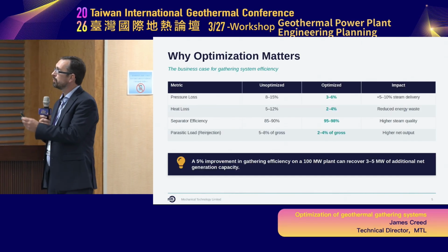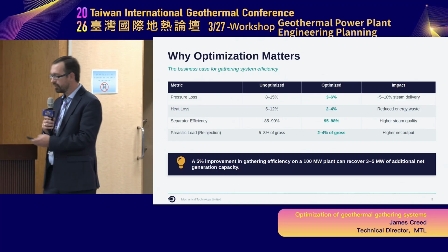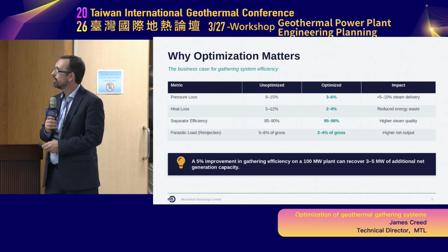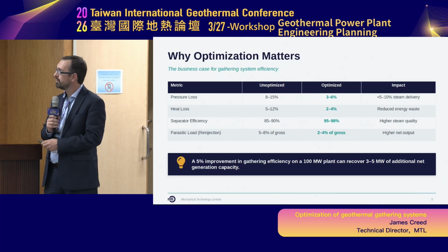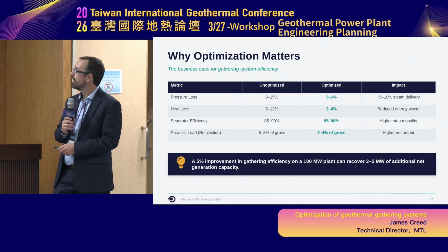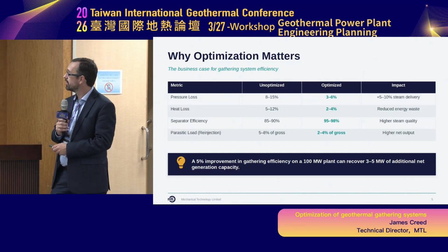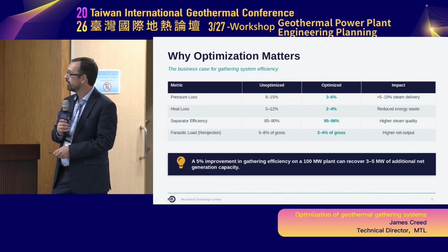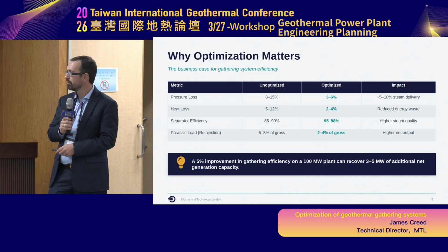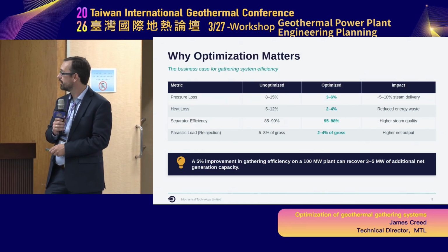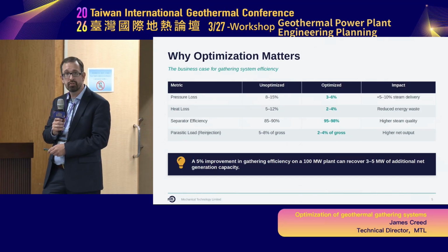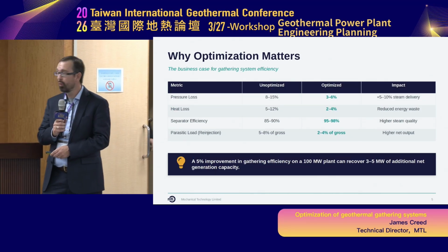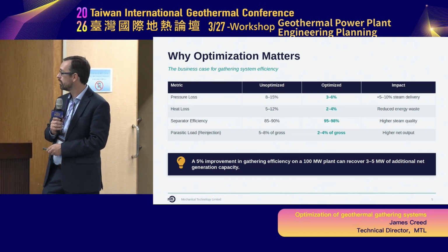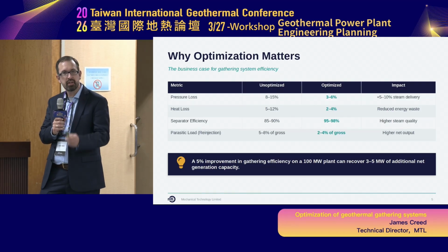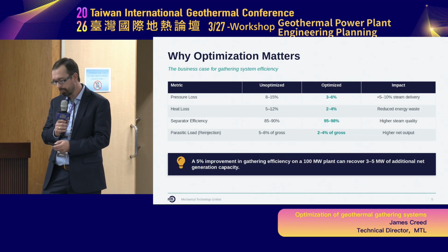So why does optimization matter? Because all the losses - pressure losses, heat losses, separation efficiency, and parasitic loads - all have an efficiency associated with them. If we don't optimize that efficiency, we don't get maximum power generation at the end. The key point is that a 5% improvement in gathering efficiency on a 100 megawatt plant can recover 3 to 5 megawatts of additional generation capacity. So what we're looking for is that extra 3 to 5 megawatts that are free - they're there to be taken, you just need to design your system to achieve it.